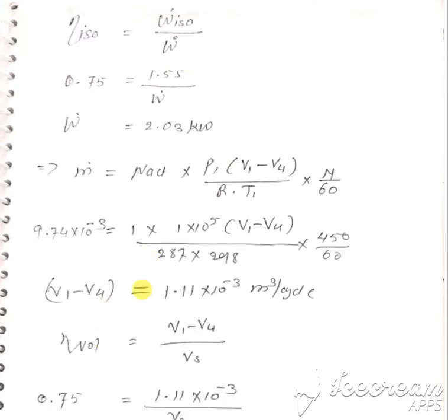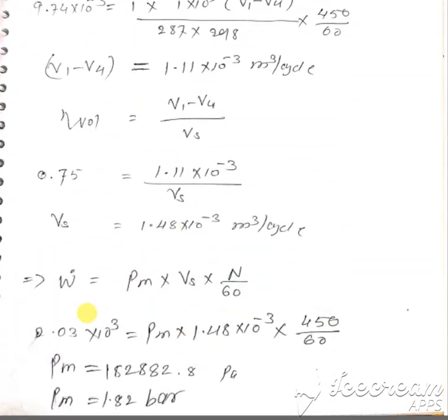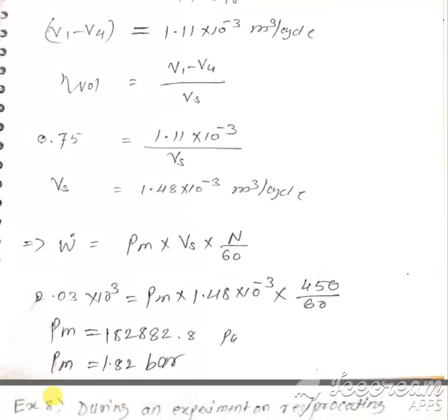We also have to calculate Vs. Volumetric efficiency = (V1 − V4) / Vs, so we first calculate V1 − V4 using: M-dot = P1 × (V1 − V4) / (R × T1) × N / 60. From this we calculate V1 − V4, then from volumetric efficiency we calculate Vs. Finally, putting Vs into W-dot = Pm × Vs × N / 60, we solve for Pm.